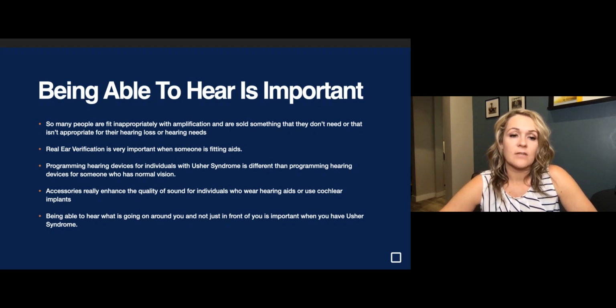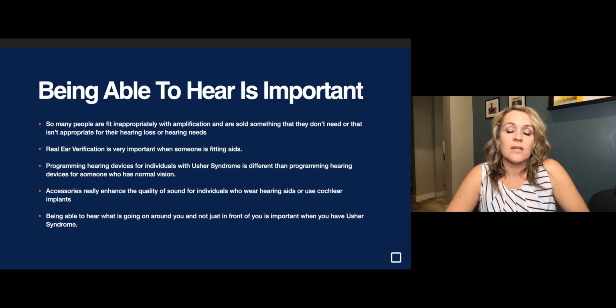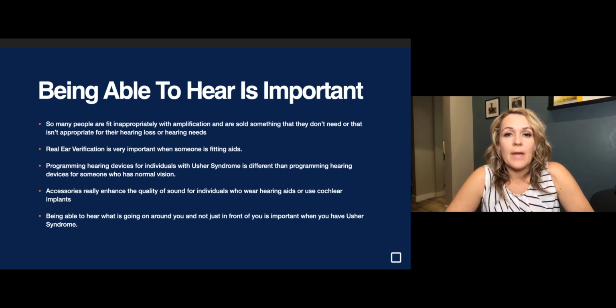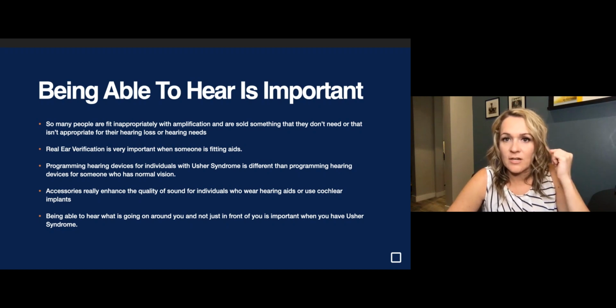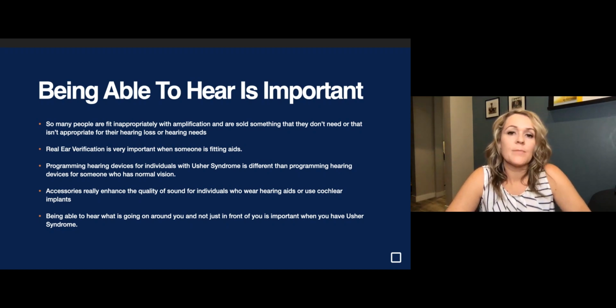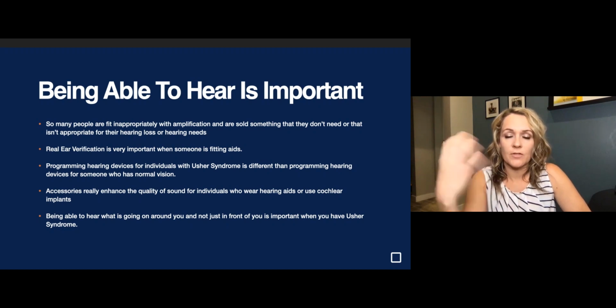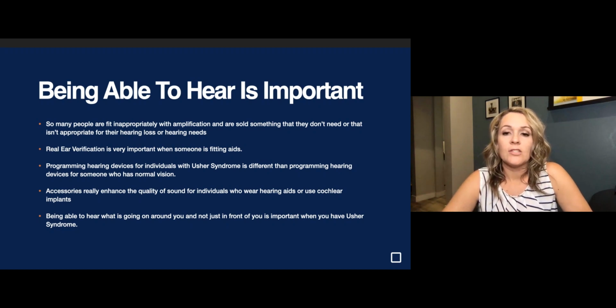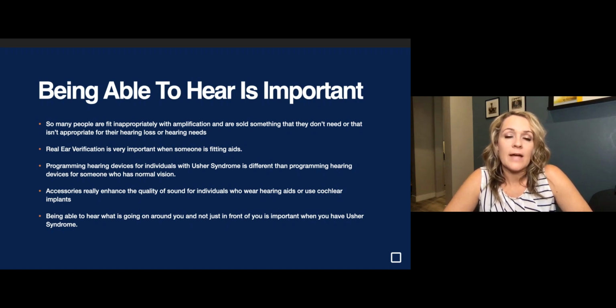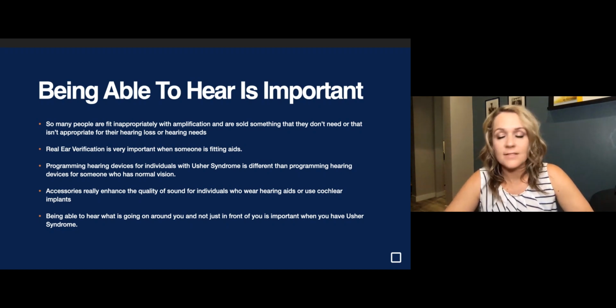Programming hearing aids in particular should be done with real ear verification. Real ear verification just means that the provider is putting a little microphone down inside your ear while they're programming that hearing aid. Typically, you're going to listen to a speaker. There's usually a speaker in front of you, and you will listen to it say, "Carrots are part of the parsley family," or you might hear just random gibberish coming out of the speaker. There are different ways that we check real ear verification depending on the equipment the provider's using, but it has to be done with a probe microphone down in the ear. If someone's putting you in a sound booth and they're just saying listen to some words with your hearing aids on, that is not real ear verification.